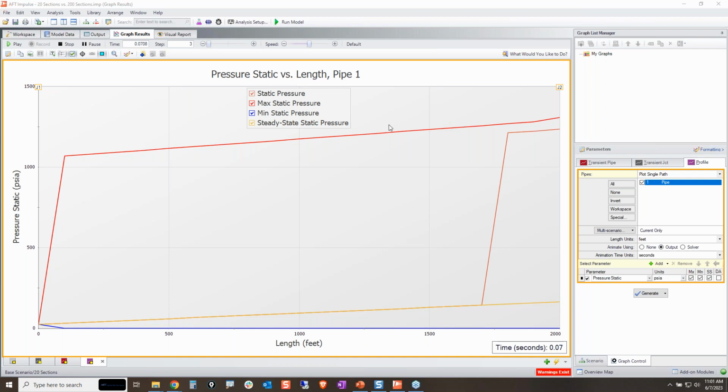So here's what's happening. That valve slams shut, our pressure surge increases, and it's traveling up the pipeline, okay? This is just basic water hammer stuff. Nothing is cavitating yet, okay? Once I get all the way to the reservoir, it's a fixed pressure that's going to reflect the wave. And so now it's reflecting the wave back to the valve. This is one wave cycle.